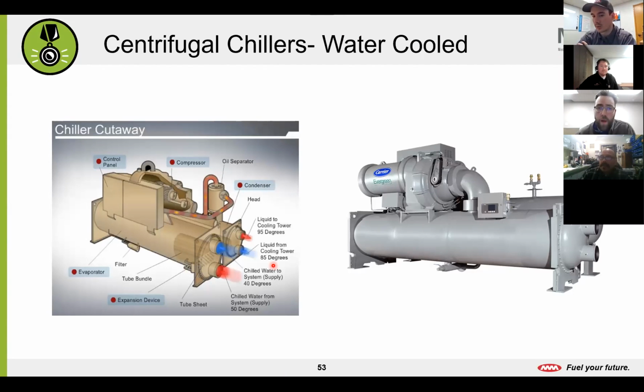Here's going to be a water-cooled chiller. You'll notice it doesn't have that big refrigerant coil on it. It doesn't have all the fans. It's just the compressor. And you'll see a condenser barrel here and an evaporator barrel here. The evaporator is where we're going to pull heat from our entering water. We want to chill down that water and supply cold water out to the rest of the building.